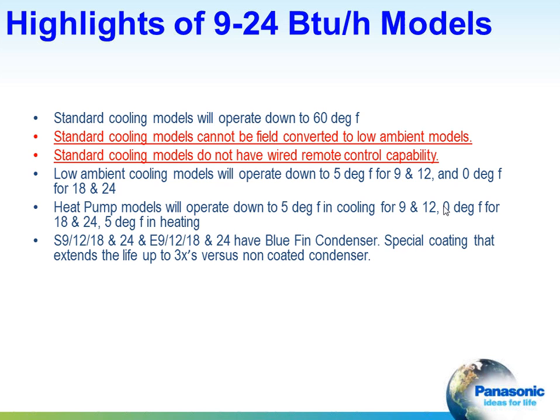Again, staying with the 9 through 24,000 BTU units, standard cooling will operate down to 60 degrees ambient. Now, we have two different lines in cooling only, standard operation and low ambient. Make sure you choose the correct unit going in right from the beginning, because the standard cooling models cannot be field converted to low ambient models. These standard cooling models also do not have wired remote control capability. They come with a wireless controller, and that's your only choice right now.